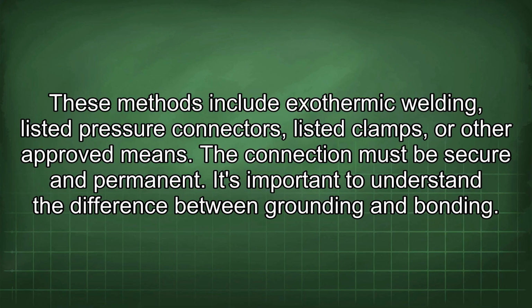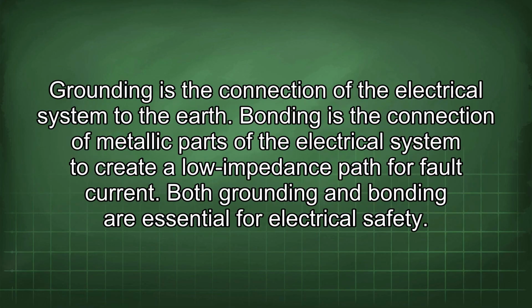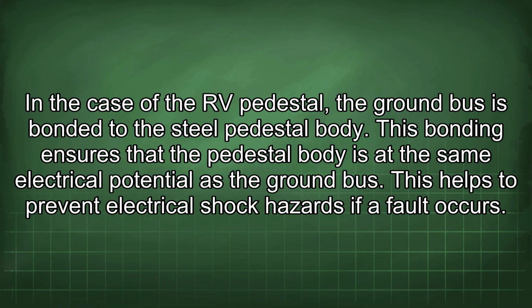It's important to understand the difference between grounding and bonding. Grounding is the connection of the electrical system to the earth. Bonding is the connection of metallic parts of the electrical system to create a low impedance path for fault current. Both grounding and bonding are essential for electrical safety. In the case of the RV pedestal, the ground bus is bonded to the steel pedestal body. This bonding ensures that the pedestal body is at the same electrical potential as the ground bus. This helps to prevent electrical shock hazards if a fault occurs.